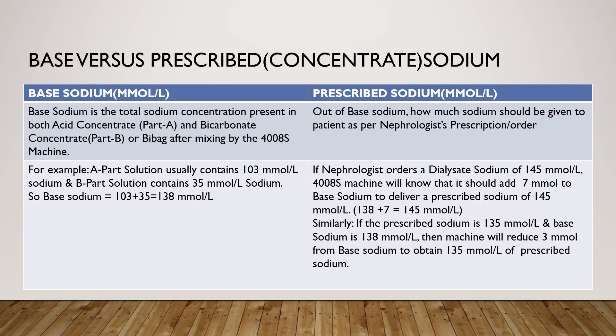Prescribed sodium is the amount of sodium to be given to a patient as per the nephrologist's prescription or order. For example, if a nephrologist orders a dialysate sodium of 145 millimole per liter, then the 4008S machine will know it should add 7 millimole to base sodium to deliver a prescribed sodium of 145 millimole per liter. Similarly, if the prescribed sodium is 135 millimole per liter and the base sodium is 138 millimole per liter, the machine will reduce 3 millimole from base sodium to obtain 135 millimole per liter of prescribed sodium for the patient.